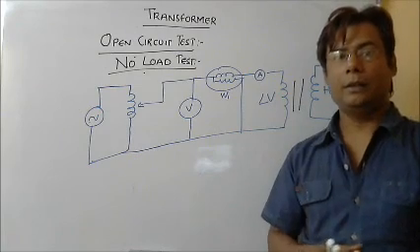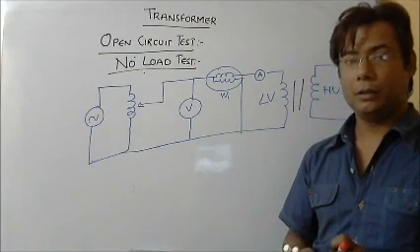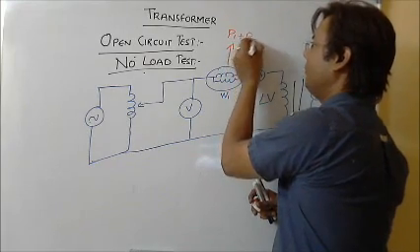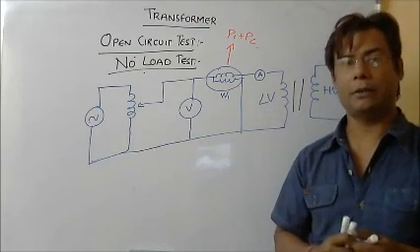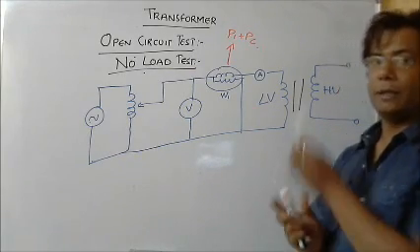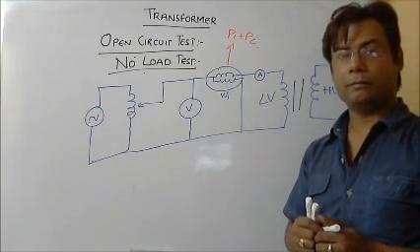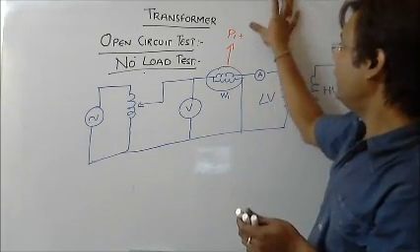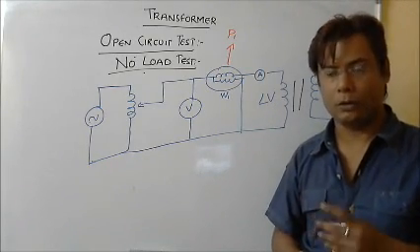W1 will continue to record the wattmeter reading, which is iron losses plus copper losses, Pi plus Pc. Since the current here is only 2 to 6% of the current which would flow when the high voltage side is loaded, the copper loss will be negligible and my wattmeter W1 will read the core losses only.